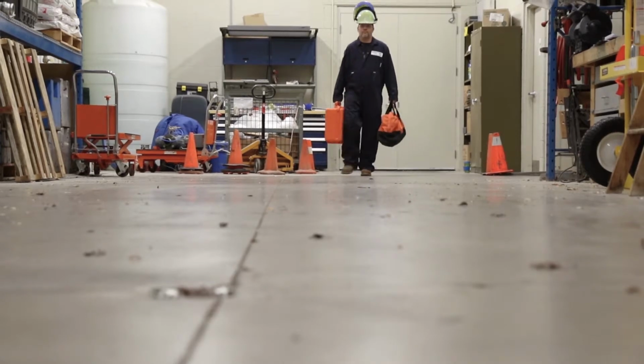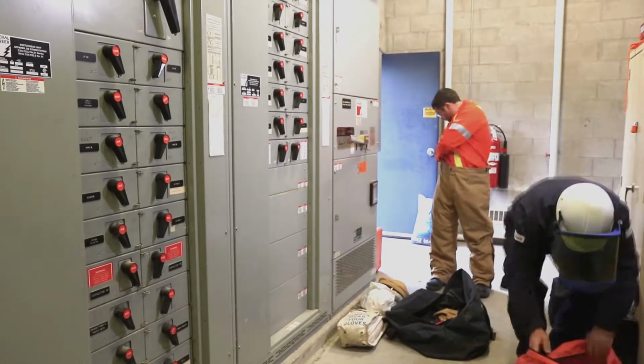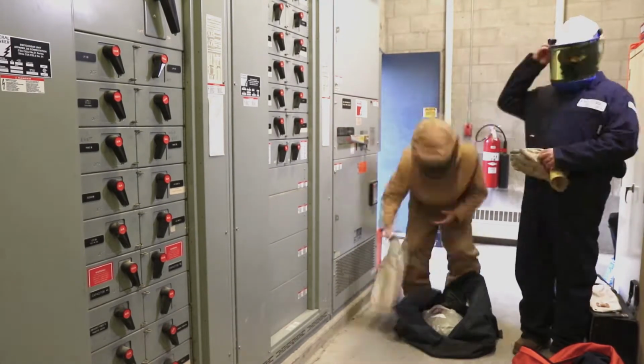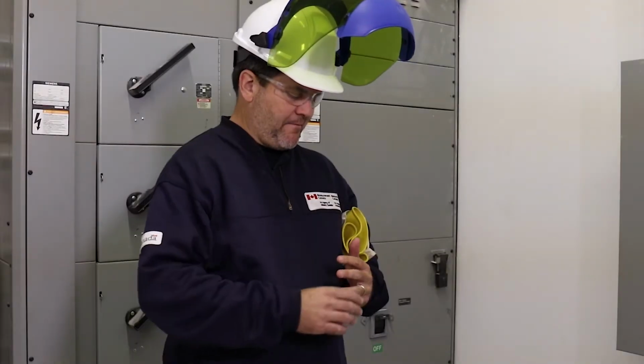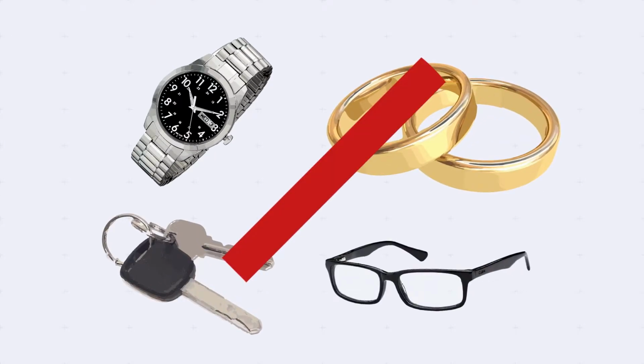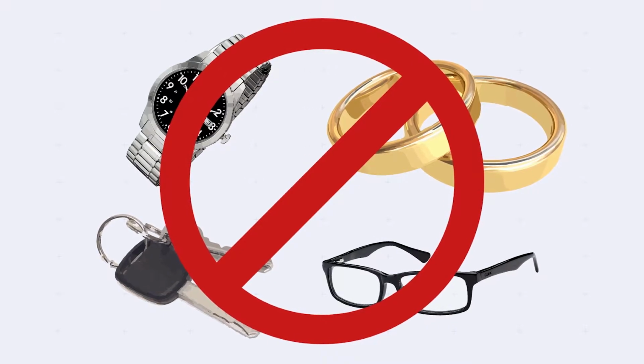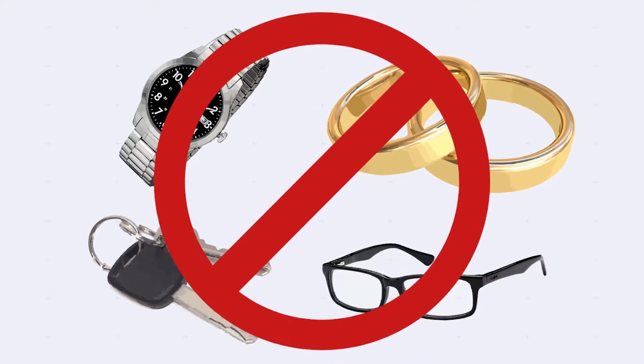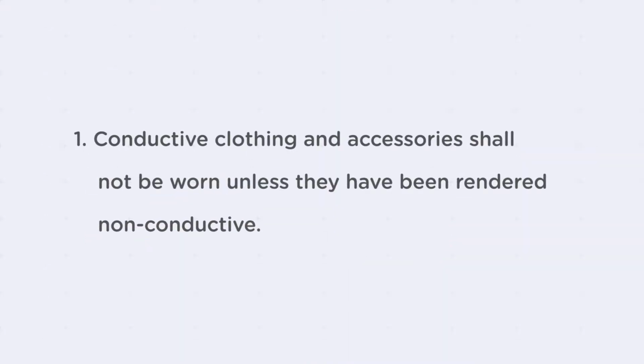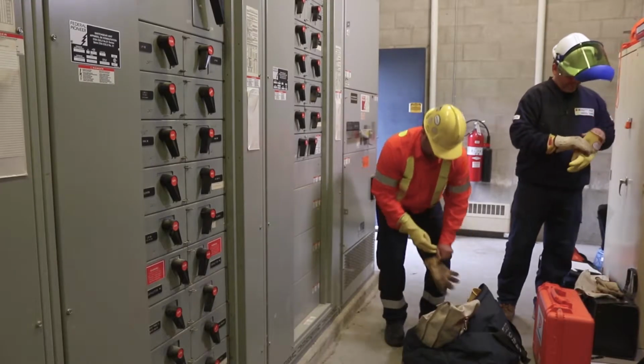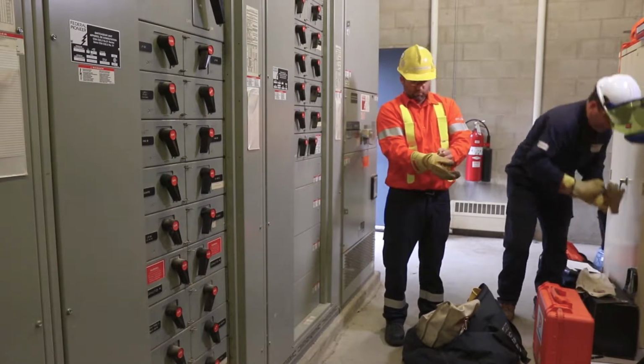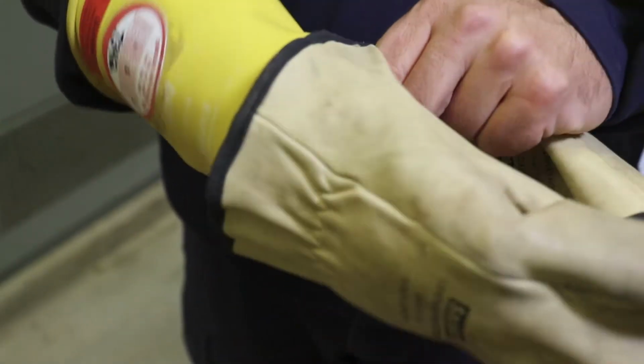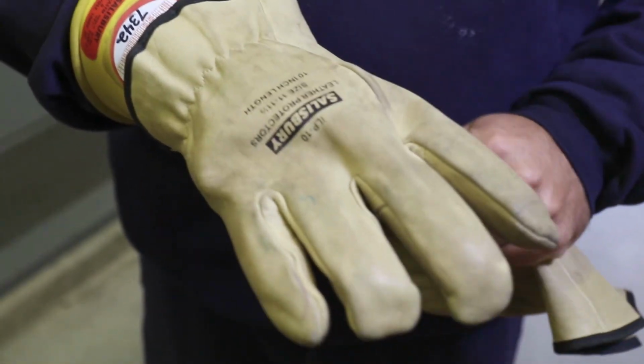As a Measurement Canada inspector, you have a responsibility to be mindful of the following general safety practices when working around exposed electrical equipment. 1. Conductive articles of jewelry and clothing, such as watch bands, bracelets, rings, keychains, necklaces, metallized aprons, cloth with conductive thread, metal headgear, and unrestrained metal frame glasses shall not be worn where they present an electrical contact hazard, unless they have been rendered non-conductive by covering, wrapping, or other insulating means. If the insulating capabilities of your personal protective equipment may be subject to damage during use, then the insulating material must be protected by a non-conductive outer covering like leather.